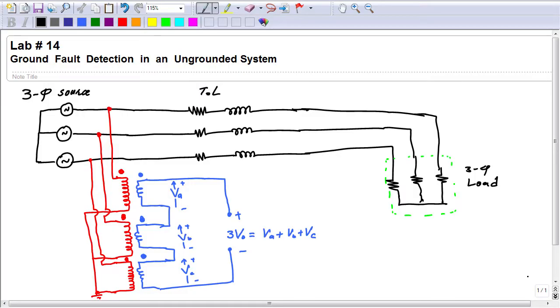Now we'll discuss how we are detecting ground fault with the help of a three-phase voltage transformer, where the primary is connected in Y grounded and the secondary is connected in broken delta formation. The circuit which I have drawn in black is a power system which is completely ungrounded: source, transmission lines, then a three-phase load. Neutrals are open, in floating condition, so that is an ungrounded system. These voltage transformers are connected such that the primary side is in Y grounded formation and the secondary, as you can see, is in broken delta.